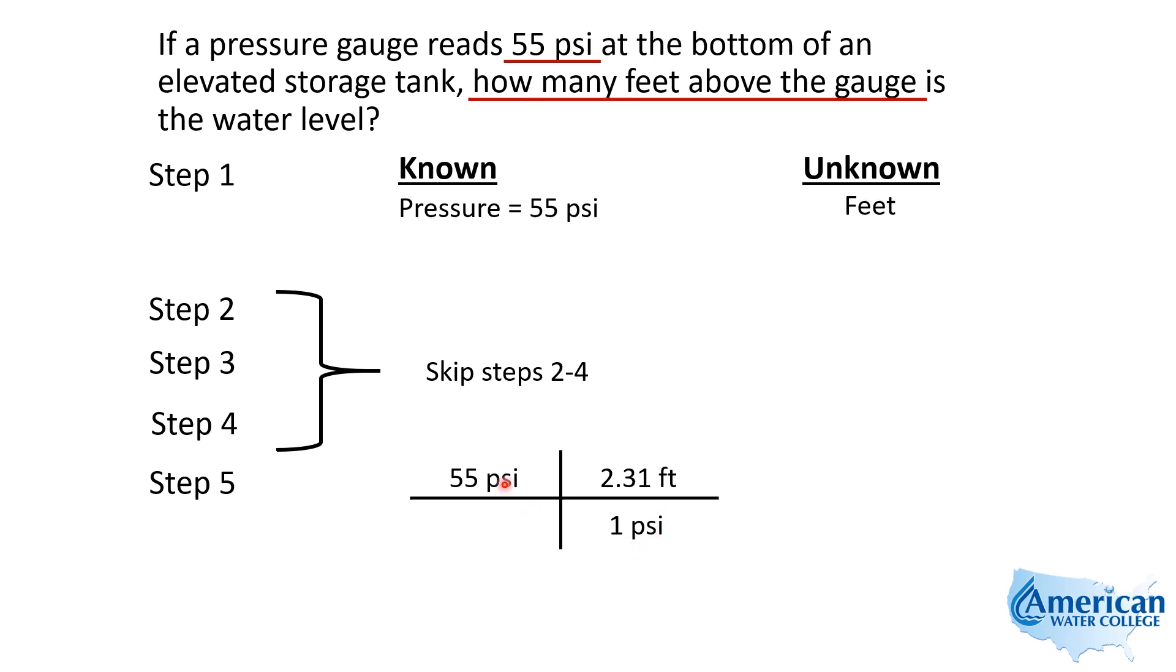This allows our psi to cancel out. So we now just multiply across. 55 times 2.31 feet will give us 127 feet of head.